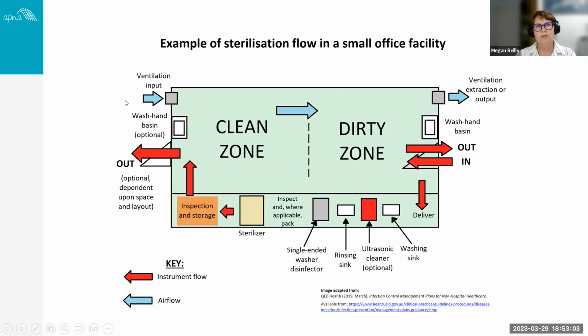But you'll also note that our ventilation system, the air should actually be going from clean to dirty. If it was going dirty to clean, then that would increase the bioburden and the risk of cross-contamination. So our ventilation requirements and our relative humidity is really important in this reprocessing area.